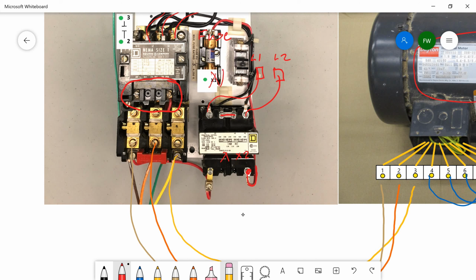So essentially that's our hot for all of our controls. That'll be 120 volts on the output. Now a good rule of thumb, but not necessarily always true, is that red wires means it's going to be 120 volts and blue wires means it's 24 volts. This is something that in most control cabinets it's good to stick to that kind of coloring scheme, but it doesn't necessarily mean that'll be the case. It's all entirely dependent upon how people have run their wires and what they've done.